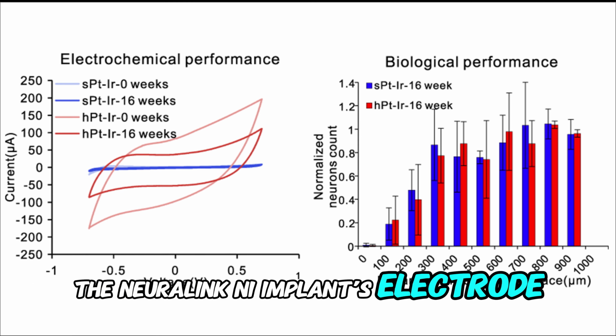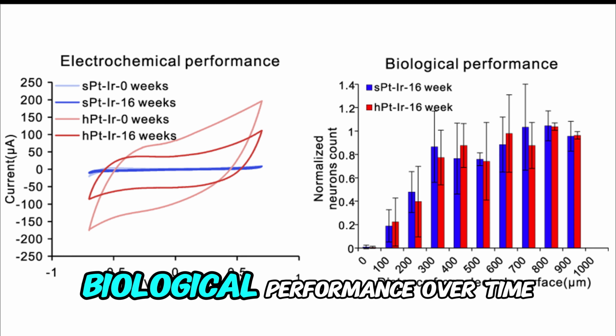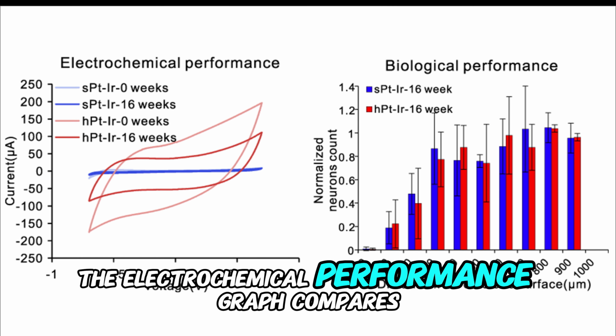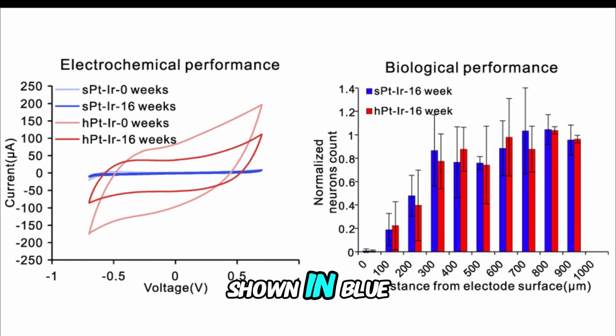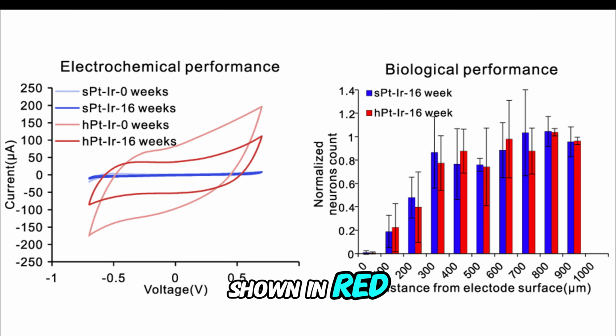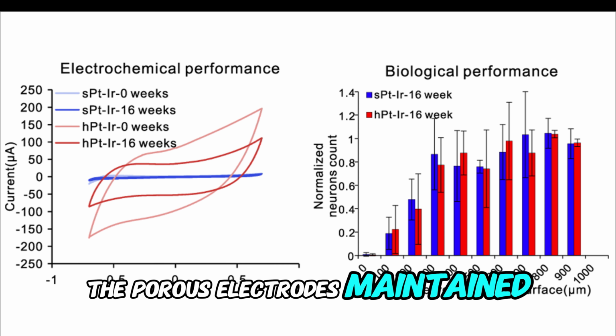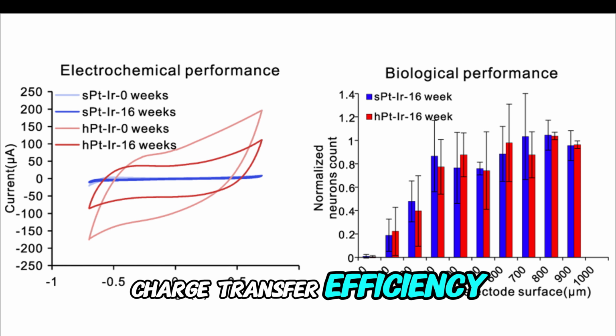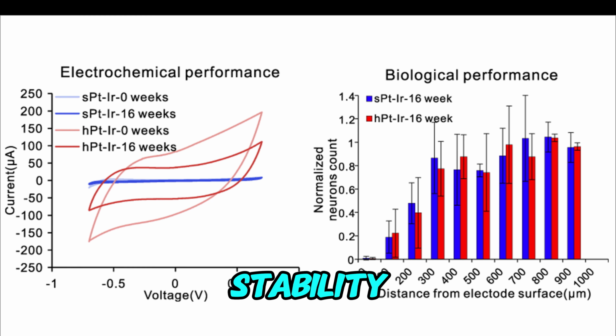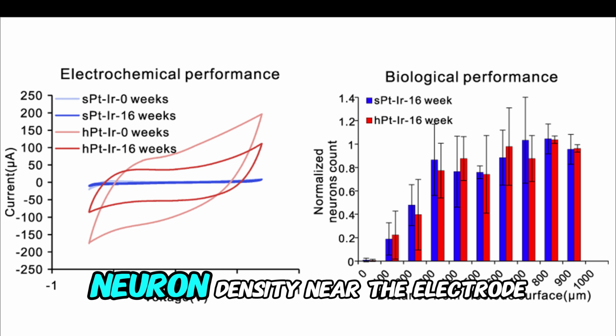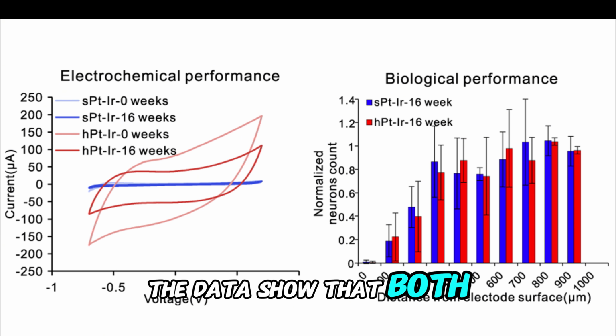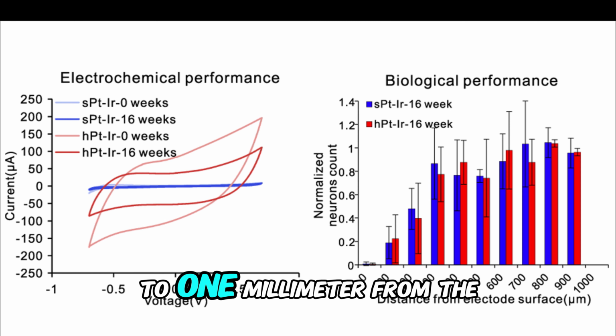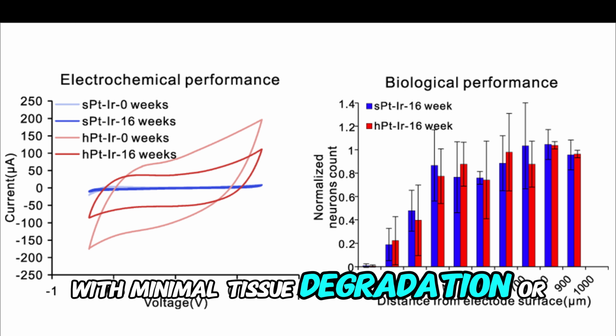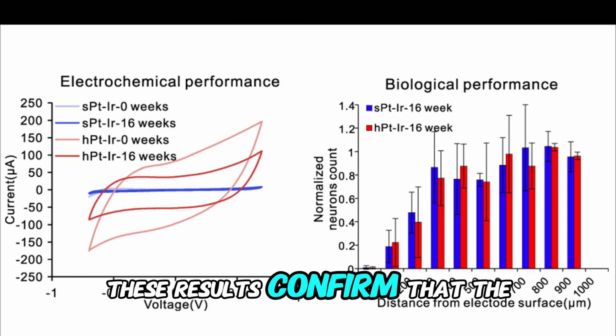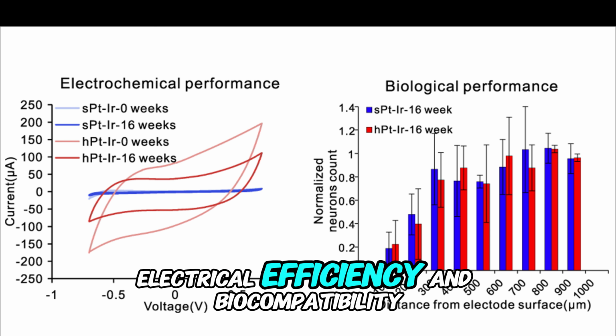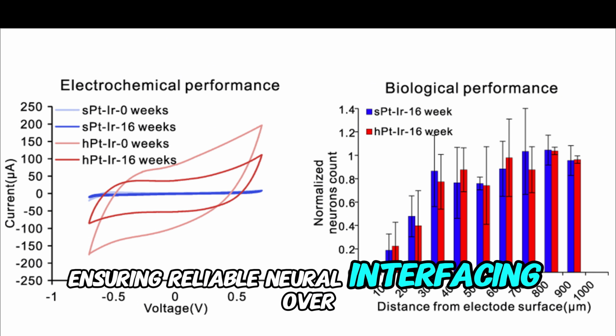The Neuralink N1 implant's electrode materials demonstrate both strong electrochemical and biological performance over time. On the left, the electrochemical performance graph compares smooth platinum iridium electrodes, shown in blue, with high-porosity platinum iridium electrodes, shown in red. After 16 weeks, the porous electrodes maintained higher current density and improved charge transfer efficiency, indicating superior long-term conductivity and stability. On the right, the biological performance chart measures neuron density near the electrode surface. The data show that both electrode types maintain consistent neural integration up to 1 millimeter from the implant site, with minimal tissue degradation or inflammatory response. These results confirm that the N1's electrode design effectively balances electrical efficiency and biocompatibility, ensuring reliable neural interfacing over extended periods.